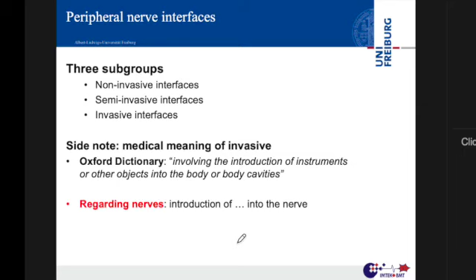So when we talk about nerves, it's important to consider that cuff electrodes, for example, which go around the nerve, are non-invasive. So that's, for example, a cuff electrode. As you said, it's non-invasive, so it's a round layer of silicone, usually, with different exposed metallic contacts, which can be gold or platinum iridium, and you put it around the nerve. You see here, for example, you have 4 different contacts on this cable, right? So you can use these 4 contacts to inject current into the nerve or to read current outside of the nerve. But if you have 150 filaments and only 4 contacts, you cannot do that much, right?